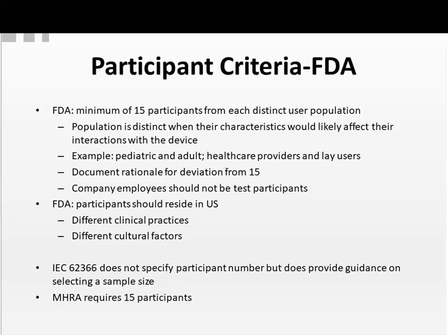Now, this is the FDA's criteria as published in their guidance. The IEC document does not specify a participant number. The MHRA also requires 15 participants. It agrees with the FDA document.